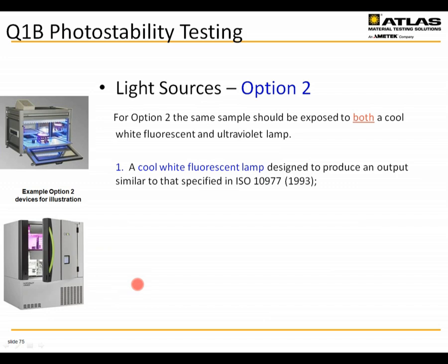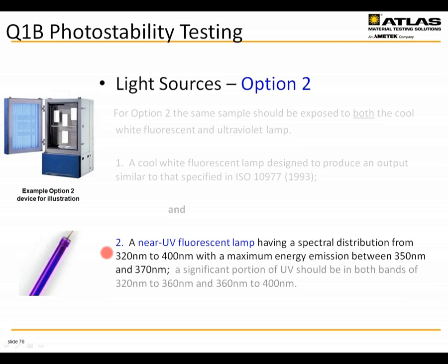The ICH guideline also provides an Option 2 light source using two types of fluorescent lamps. One is a cool white fluorescent lamp designed to reproduce the spectra in ISO 10977 — a visible daylight lamp. Then it requires a second separate UV lamp — a near-UV fluorescent lamp with a peak spectral emission between 350 and 370 nanometers. In some instruments, it's possible to combine both lamps into one instrument during one exposure, but more commonly you would have two separate exposures: one using the visible cool white fluorescent lamp and one using the UV lamp.